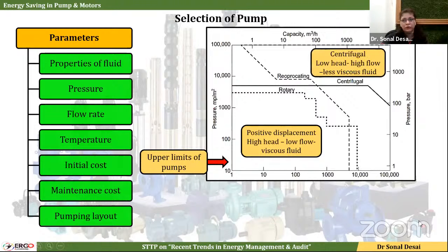This is a general diagram showing in which case one should go with a centrifugal pump. When there is a low head, high flow requirement and a less viscous fluid, go with the centrifugal one. If high head is required, with low flow rate and the fluid is viscous, go with the positive displacement one. It can be a piston pump or a vane pump.